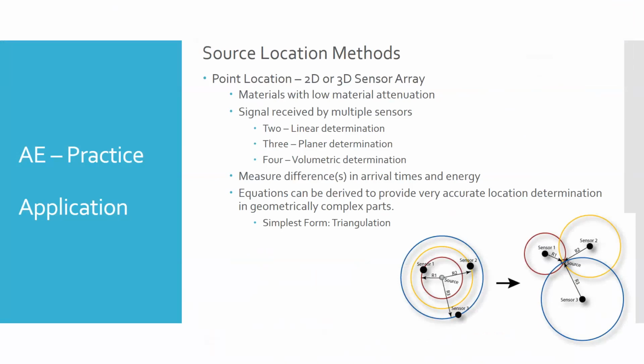With geometrically complex parts, you can build that geometry and complexity into the equations and algorithms used to determine location, since they're not just linear. If a crack forms here, the sound isn't going to travel in a straight line to this sensor; it has to travel up and over, while to these other sensors it travels a straight line. So we can look at the time difference between these three sensors and tell there's a crack here, because a crack down here will hit one sensor first, another second, and another third. If we had another sensor somewhere else, you can see the more you add, the better your resolution becomes.